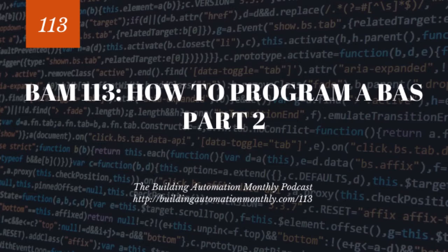And the way you have your sequencer set is that it needs to turn on stage 1 first. So you could go and make your sequencer where even if stage 1 is off, it turns on 2 and 3 and 4. That may work. That may be a bad scenario, depending on how you're supposed to control the systems. So with that being said, sequencers can be very, very confusing.